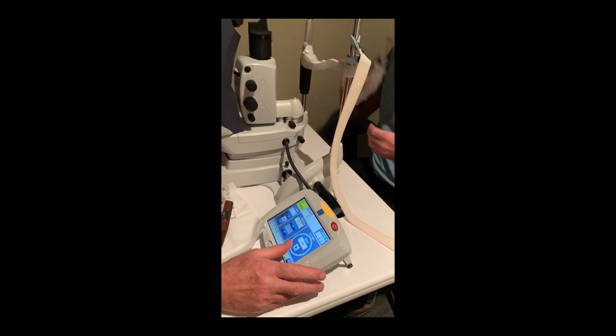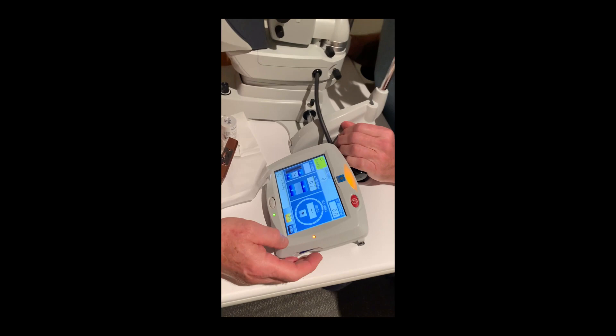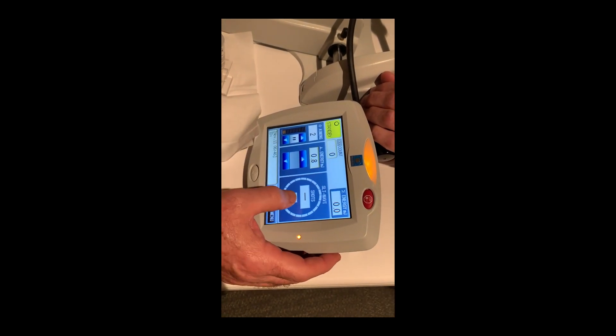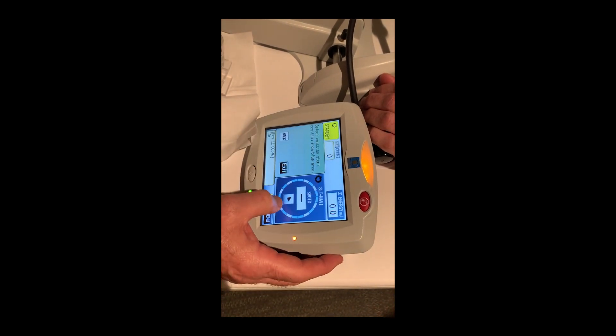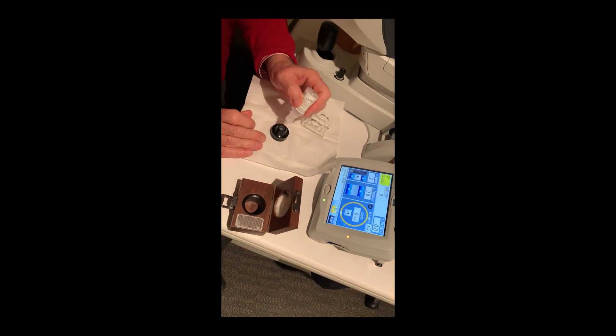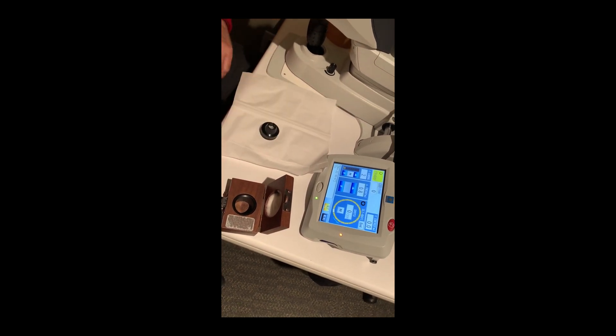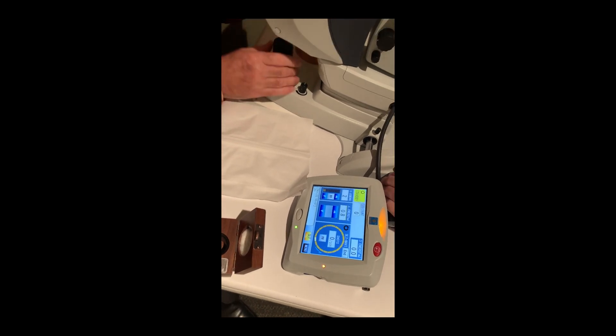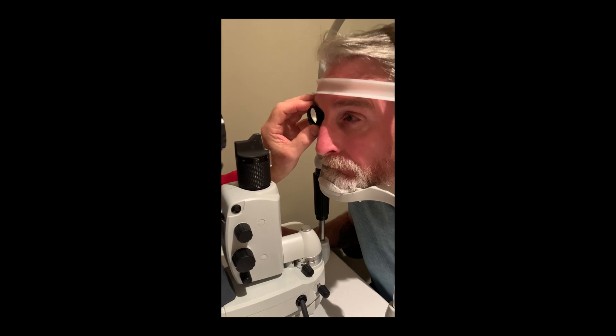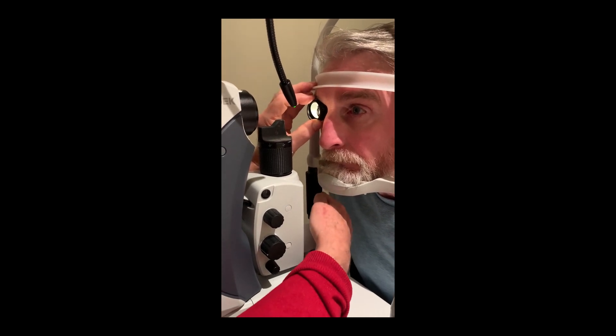When we look at any of the lasers and talk about engineering, these are the things we take for granted — we usually don't think about what's under the hood, but it's important. There's a laser component, a control panel, optics, and a delivery system. We want to be sure that every time we actuate the laser, we're getting that precise laser energy we've set up for. If I'm setting for 0.7 millijoules, I want to get 0.7 millijoules every single time. I also want the energy to be evenly and homogeneously distributed across the laser beam — no peaks and valleys. I want a system that's stable and works each and every time.